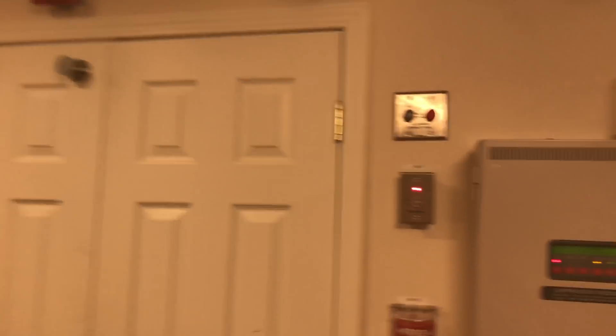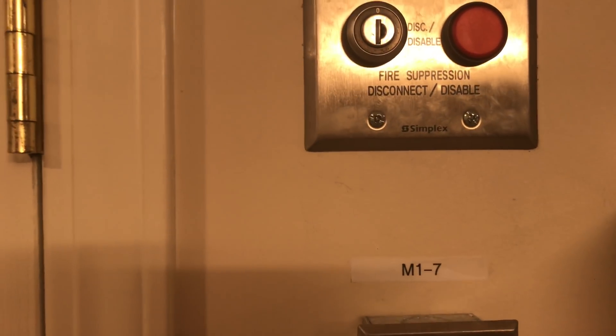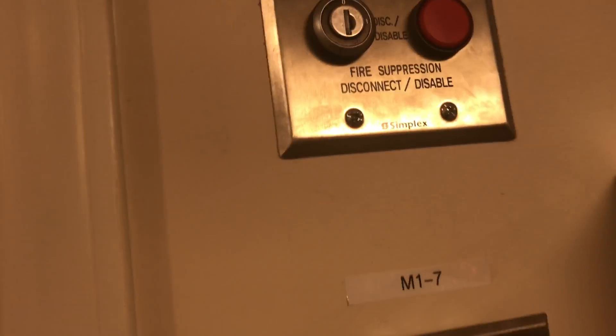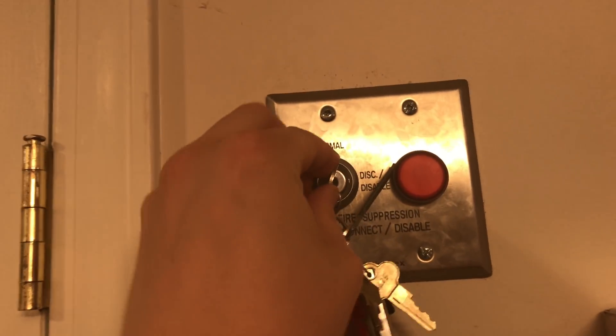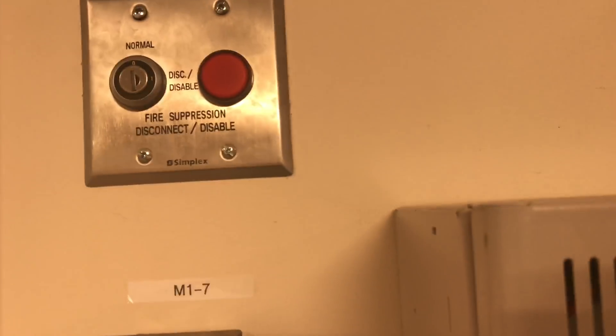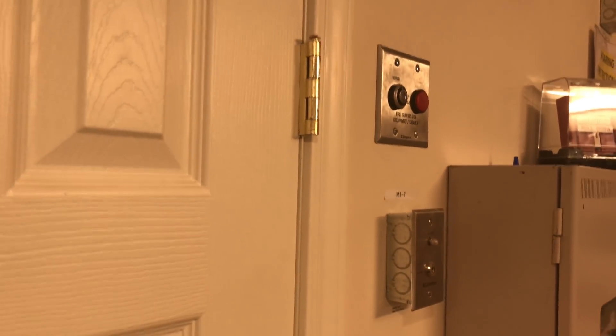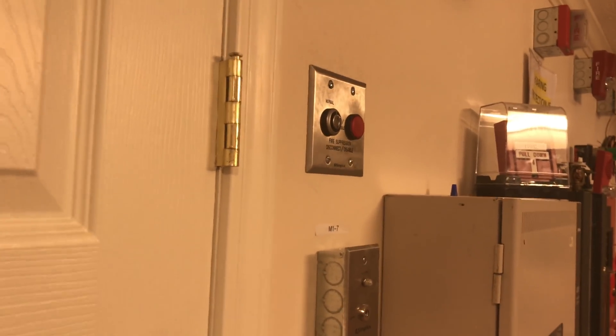So now we wait. You are probably noticing this is a new switch up here. This is what I use to disconnect my ID net channel to change out devices. It is just for a fire suppression system, so this is like a service switch if you want to disable it to do some work on it. When you turn the key the light comes on and then it cuts off my ID net channel, and then all the troubles will start to come up on the panel from weak no answer, because it is basically acting as a switch. That way I can change devices out without completely shutting down the panel and having to reset it every time.